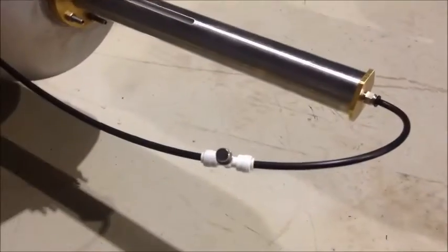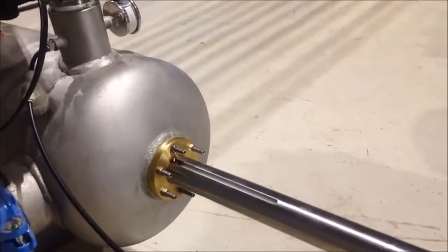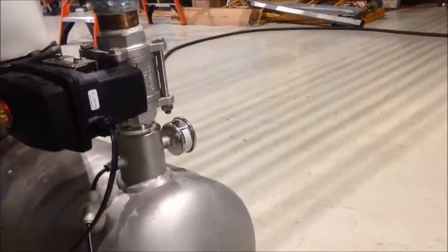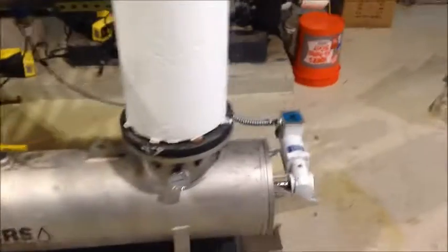We observe the hydraulic tubing is installed correctly, and the flush outlet here. We will be coming back to check that there is no back pressure at that location during backwash.